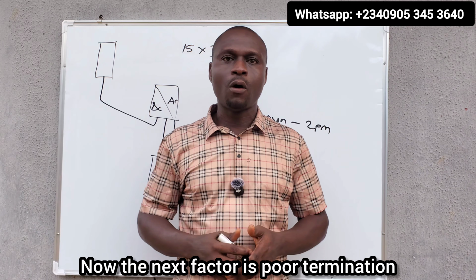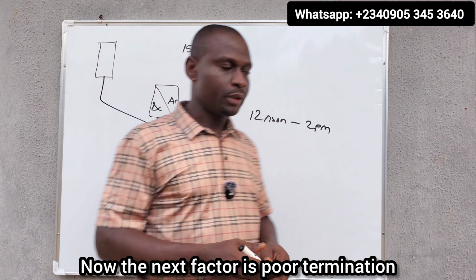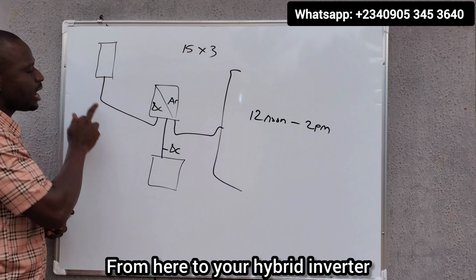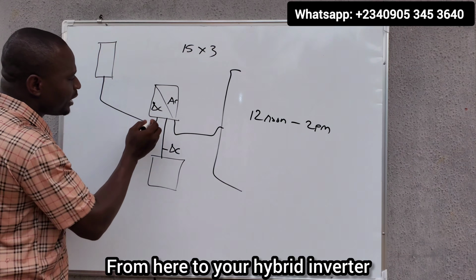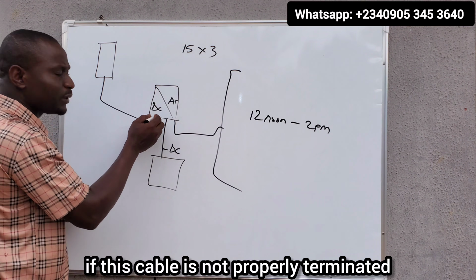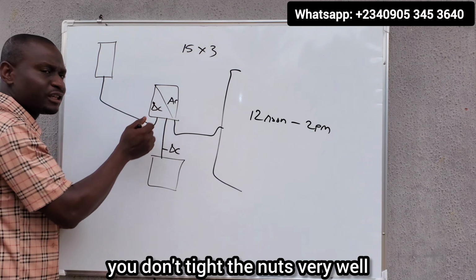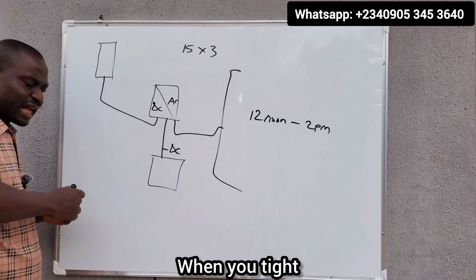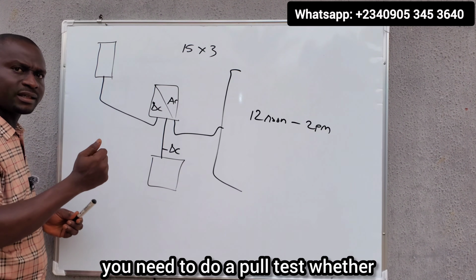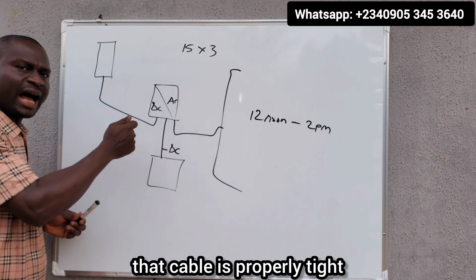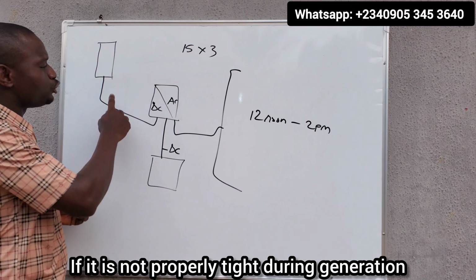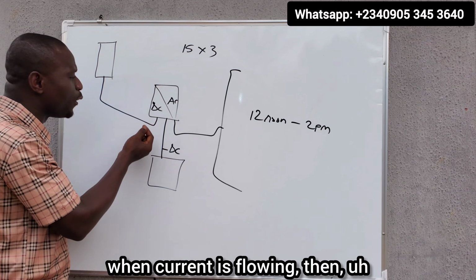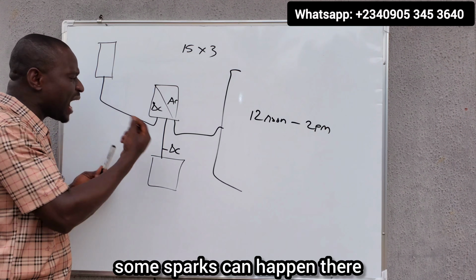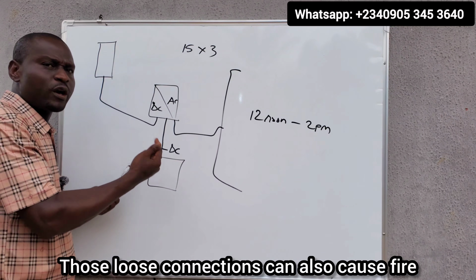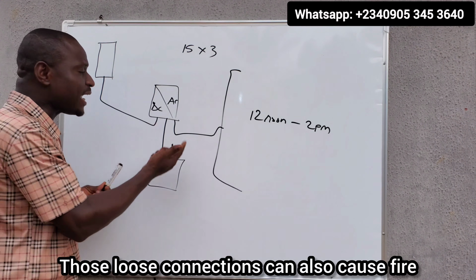Now the next factor is poor termination. From here to your hybrid inverter, if this cable is not properly terminated and you don't tight the nuts very well, when you tie it, you need to do a pull test to check whether that cable is properly tight. If it is not properly tight, during generation, when current is flowing, some sparks can happen there. Those loose connections can also cause fire.